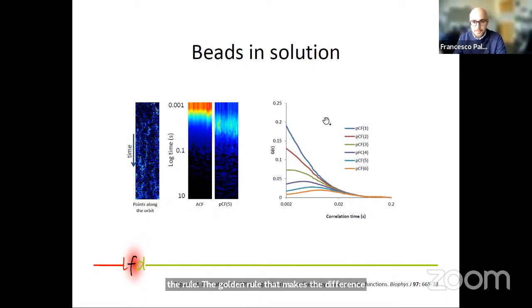So what's the difference between RICS and PCF? Usually RICS requires a much slower type of scanning, while for PCF the faster you go, the better. There is some trade-off for signal to noise ratio, and this depends on your system, but this is more or less the golden rule that makes the difference between RICS and PCF in terms of instrument settings.